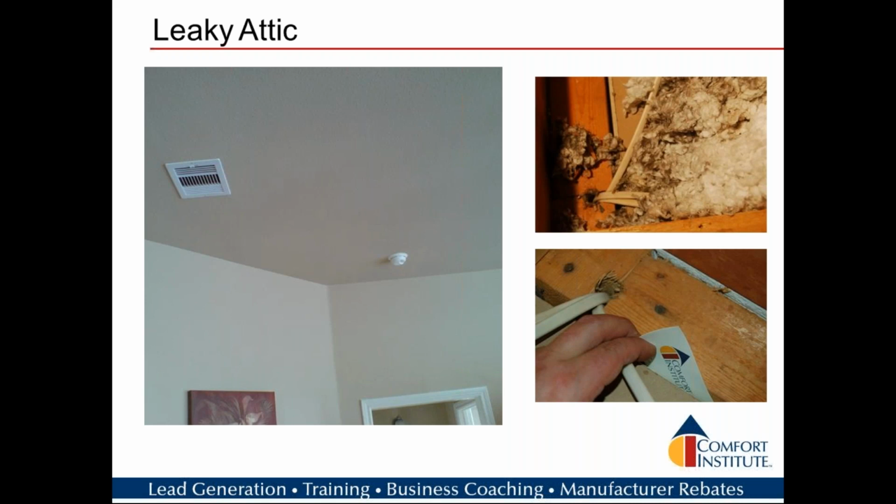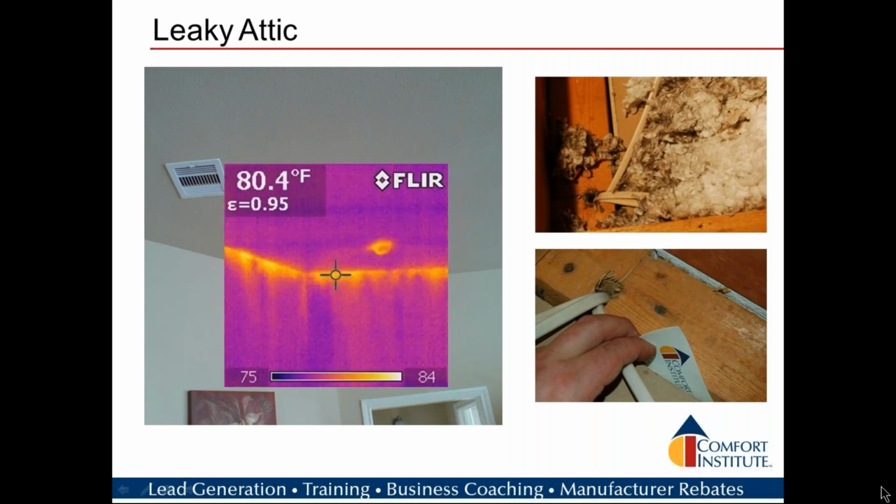How does it get there? Hey, we've got a lot of holes in houses: plumbing holes, wire holes, and just the fact that when you put the house under a negative pressure and you start smoking, you'll find where all these holes are. These are just the top plates. If you look on the right-hand side there, you'll see the gap between the boot and the sheetrock. Very common. Over a period of years, when the house dries out, the wood will shrink up, but the sheetrock doesn't. We get gaps all the way across the top of that. That's how that air comes into these homes, and it can make these second floors very uncomfortable.